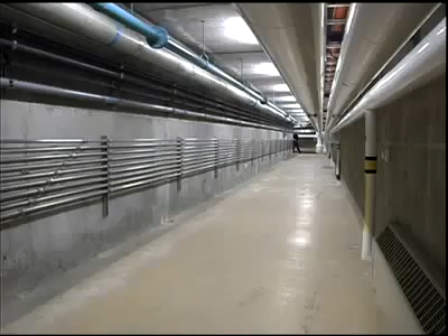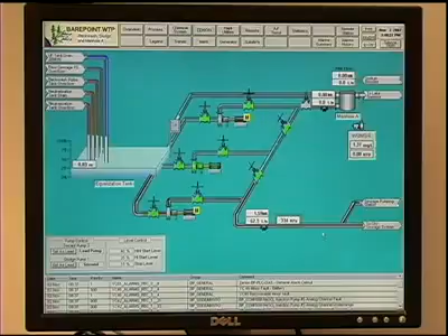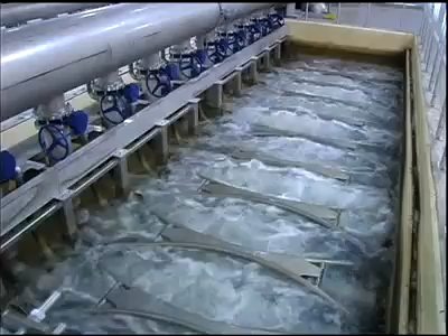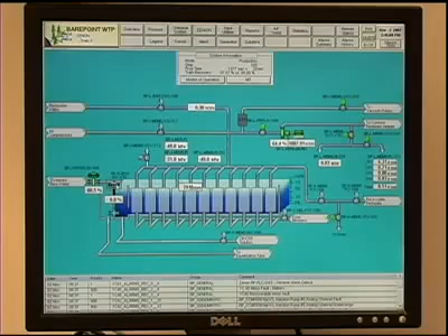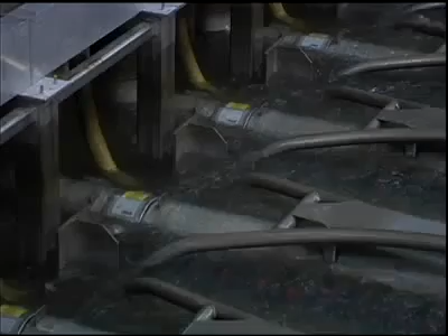In order to protect the staff from Thunder Bay's sub-freezing winters, workers travel from one building to another via an underground tunnel. As water flows through the facility, Wonderware InTouch software is utilized to operate a series of pumps and control valves as the water makes its way to the ultrafiltration membrane room. This is where Wonderware's graphical interface is particularly effective. With the ultrafiltration trains on a backwash cycle, there is a representation of the bubbles and the aeration throughout each of the filters. On the Wonderware screen, the operator gets a representation of exactly the bubbles and the tank drain and the levels of that process.